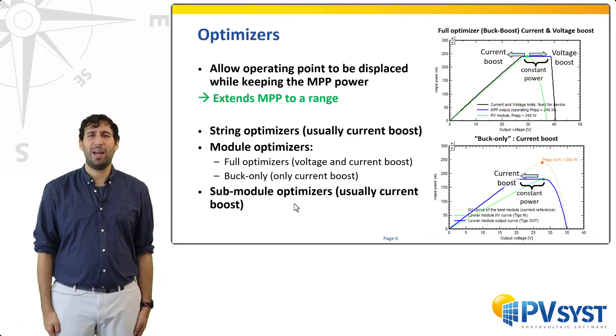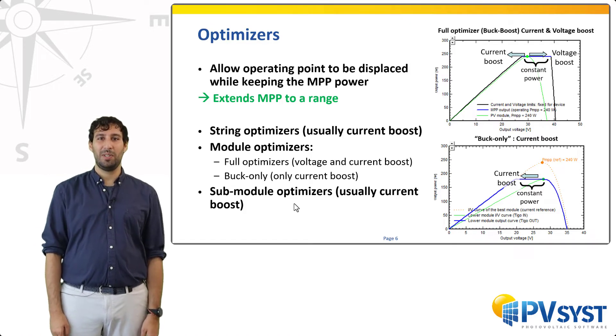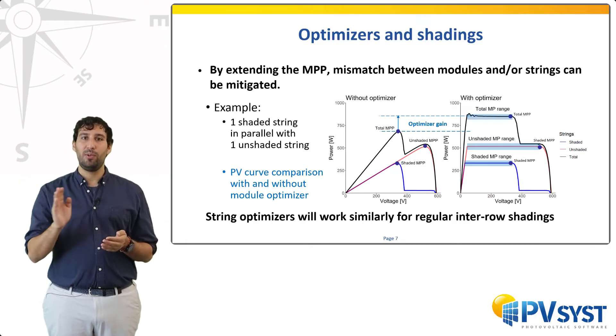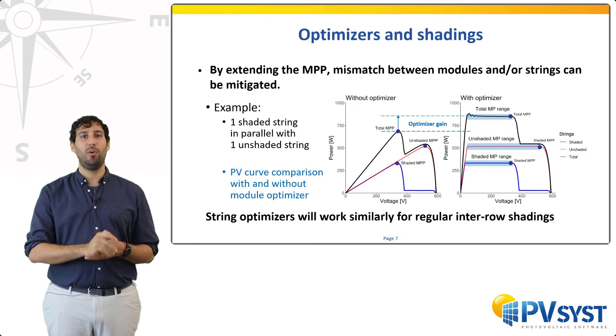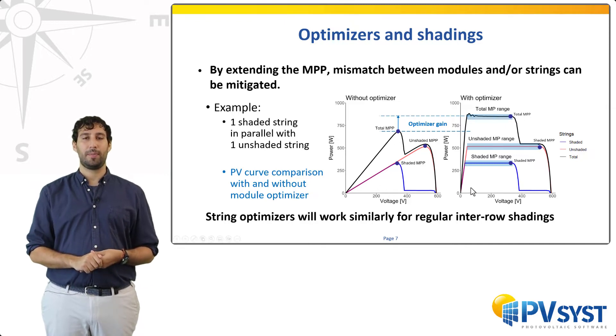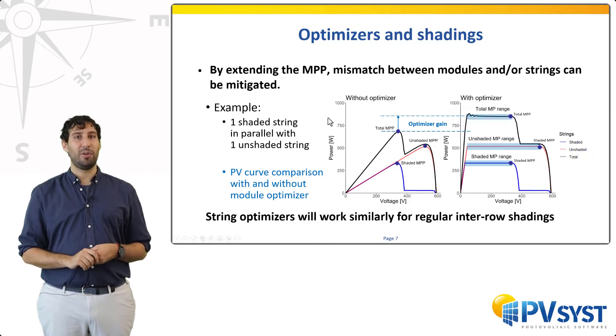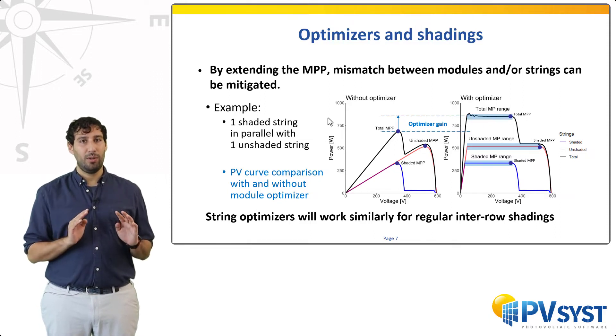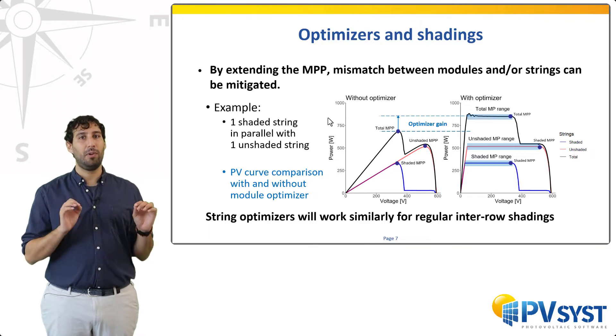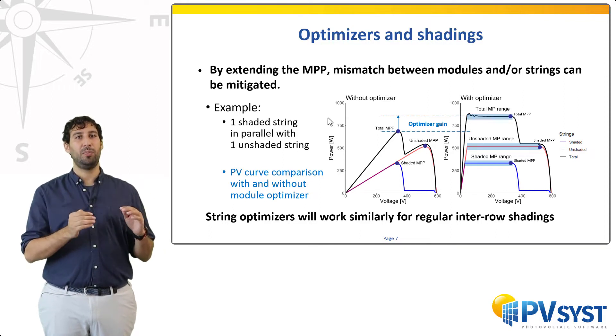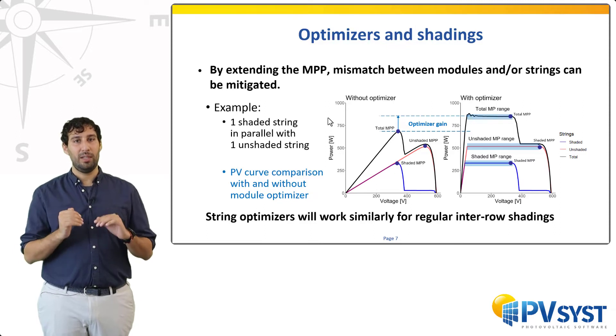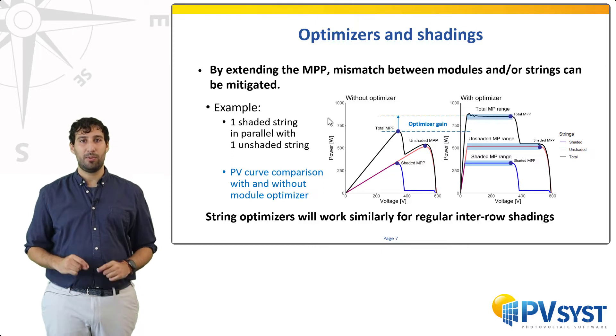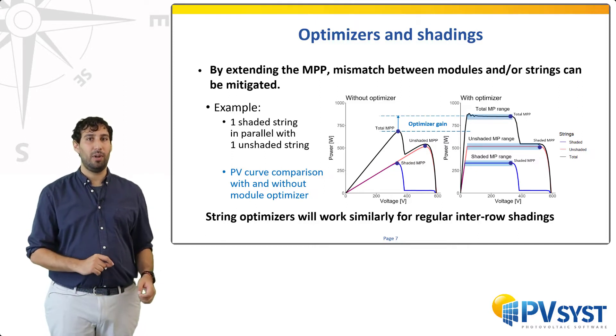It is easy to understand how optimizers improve production in the context of shadings. By extending the MPP to maximum power ranges, it is easier to find an operating point that fits all maximum powers of the individual components. In our earlier example of two strings in parallel, one shaded and one unshaded, one can see that using module optimizers there is now a range of voltages that allows the maximum power to be the sum of both individual maximum powers. You could reach the same results with string optimizers, and slightly better with sub-module optimizers.